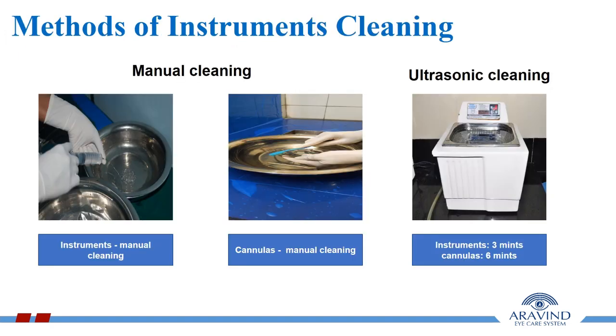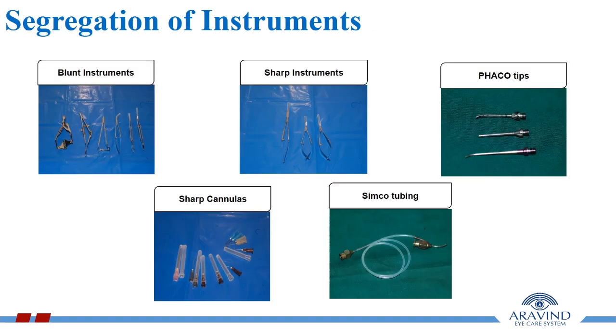Methods of instrument cleaning: manual and ultrasonic cleaning. In manual cleaning, we clean the instruments and cannulas by hand. For ultrasonic cleaning, we place the instruments in the machine for 3 minutes and cannulas for 6 minutes.